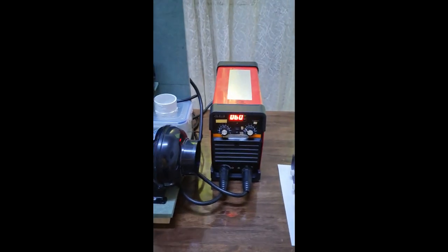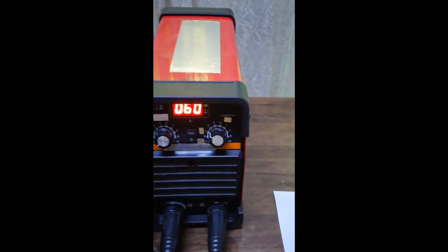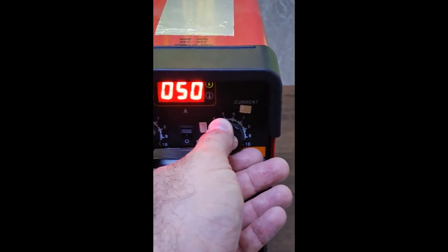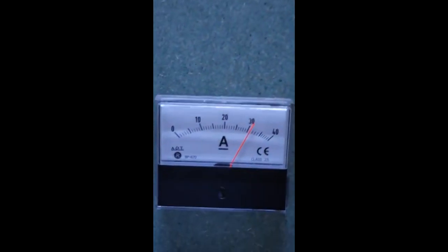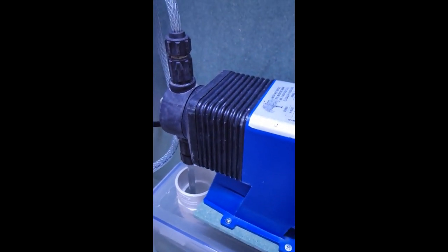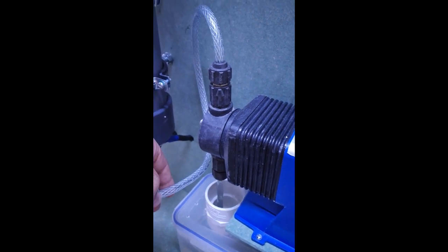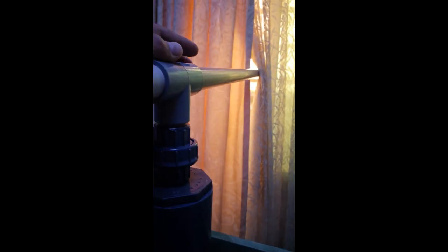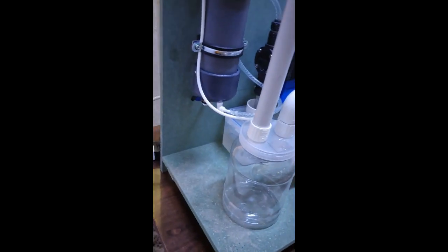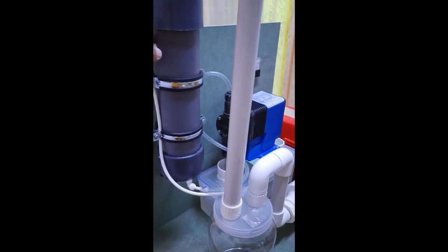Now as we can see, we turn on the power supply. We have to reduce it to 30 amps as shown on this indicator. The dosing pump is working properly and it starts to dose the sodium chloride solution into the reaction chamber. Now there are gases as we know then exhausted through the pipe, and now we'll just give it a little bit of time till the chamber is filled up with the solution.